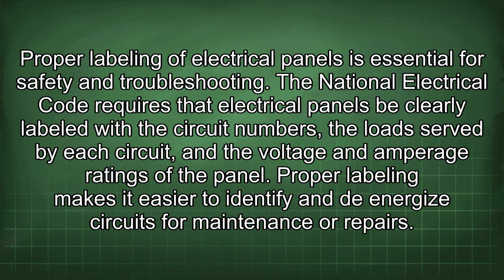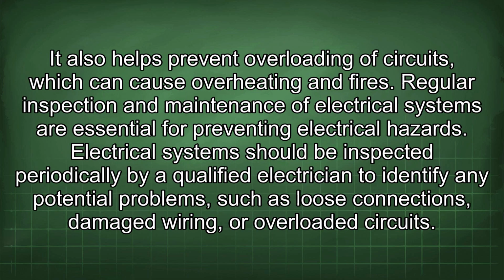Proper labeling of electrical panels is essential for safety and troubleshooting. The National Electrical Code requires that electrical panels be clearly labeled with the circuit numbers, the load served by each circuit, and the voltage and amperage ratings of the panel. Proper labeling makes it easier to identify and de-energize circuits for maintenance or repairs. It also helps prevent overloading of circuits, which can cause overheating and fires.